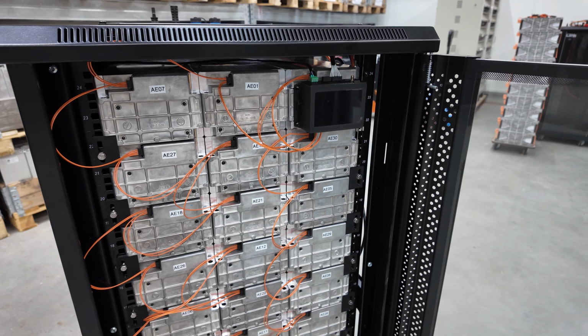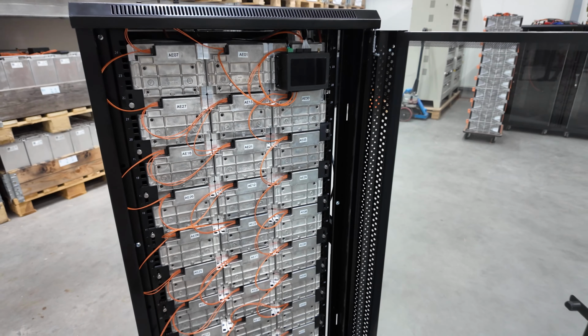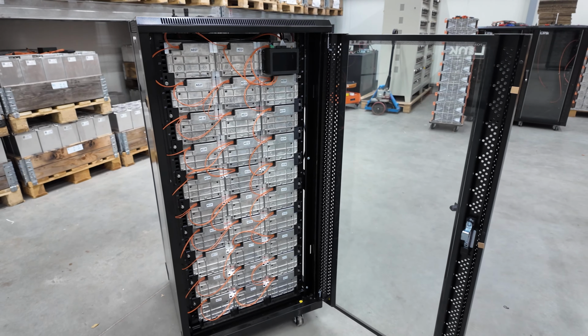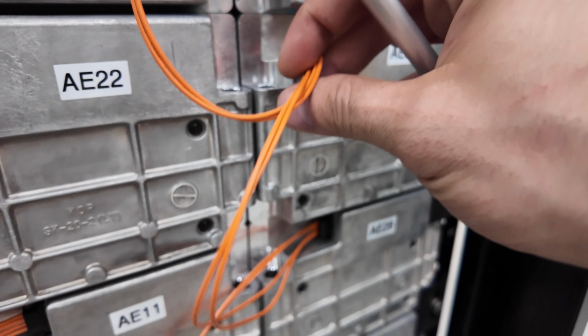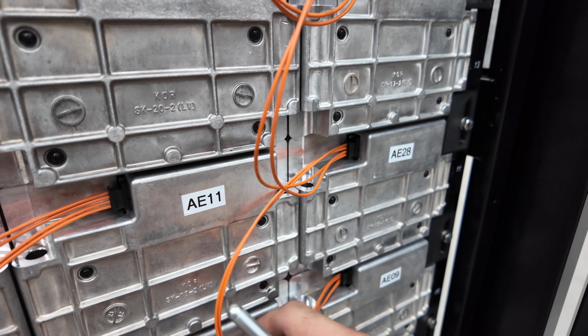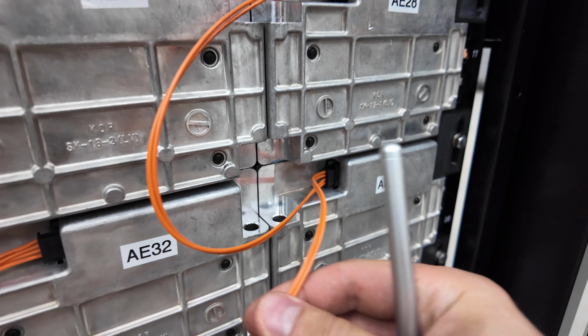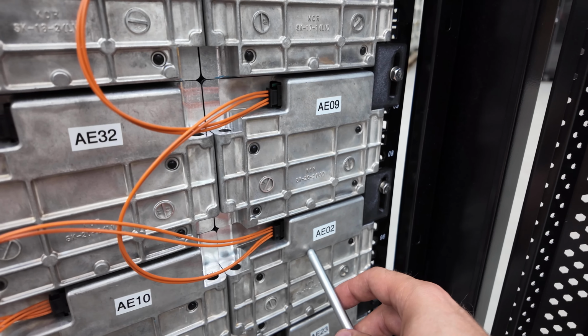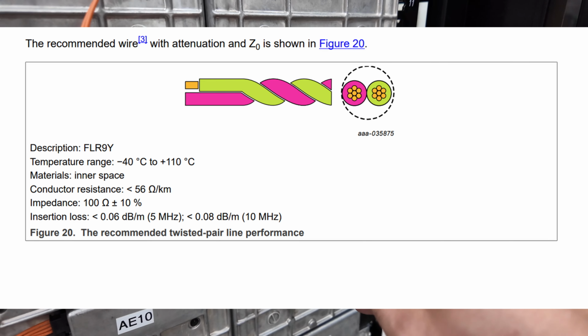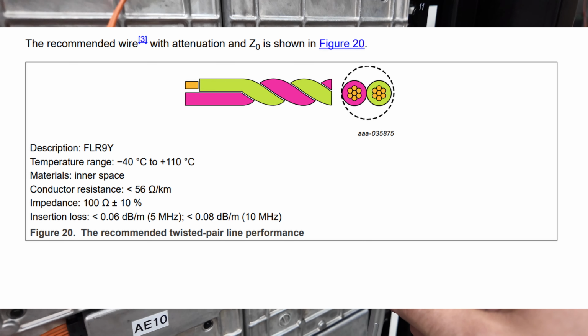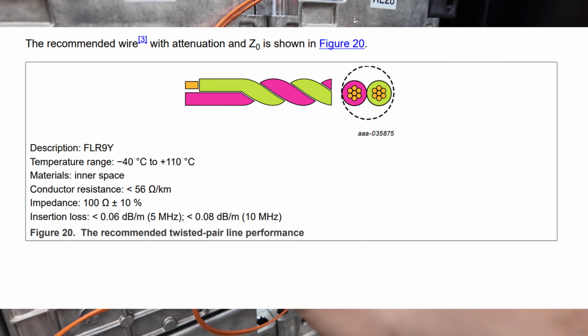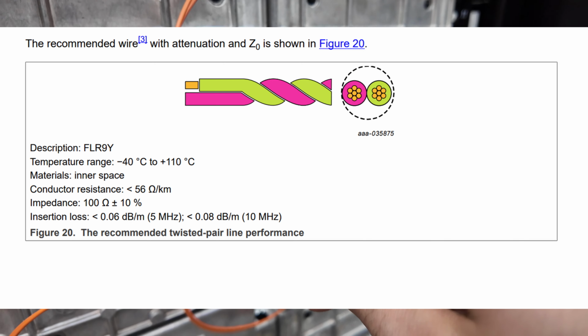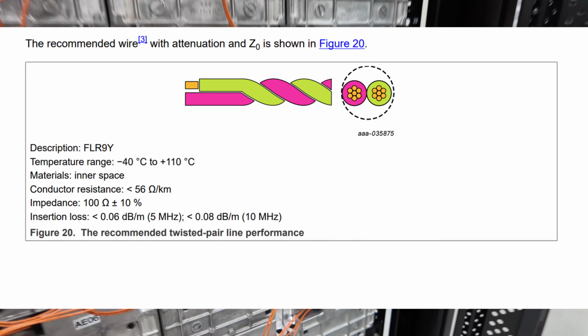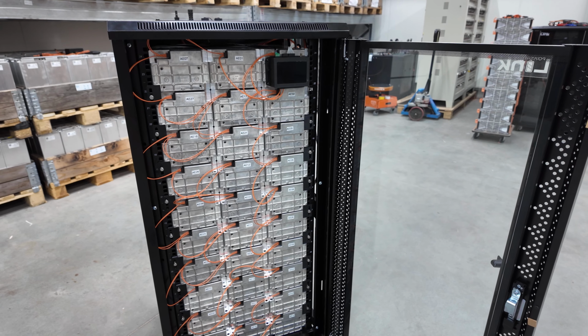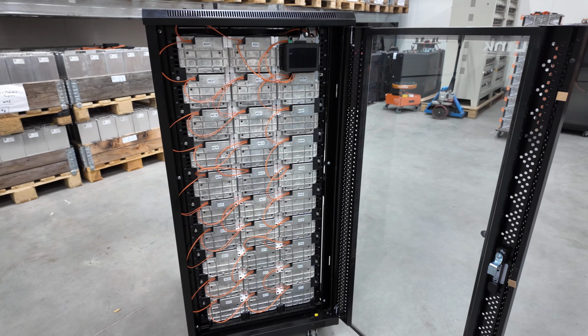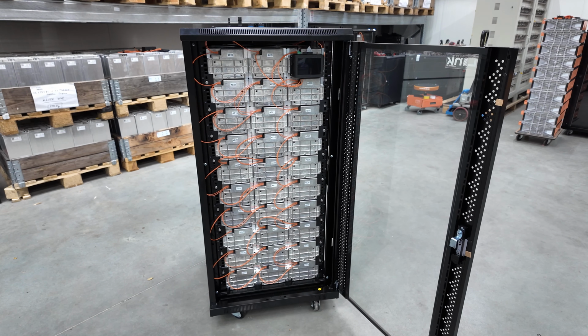After that we connect it directly to the Taycan battery modules, 15 battery modules per string, using TPL1 communication protocol and the wire I showed you previously. The very important part about this wire is that it has to be the correct length, correct resistance, correct inductance. This is specified in the TPL1 protocol datasheet provided by the chip manufacturer we use, and we follow the instructions in this datasheet to make that kind of wire loom. It cannot exceed a certain length, so we prepare it within specification.